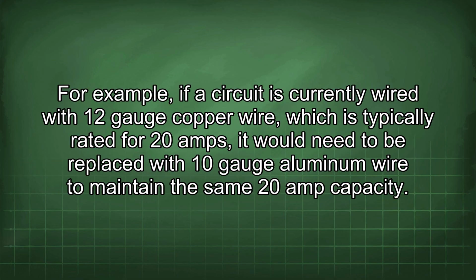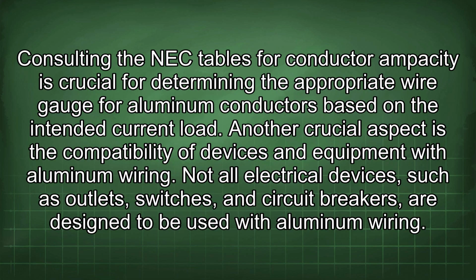ampacity. For example, if a circuit is currently wired with 12-gauge copper wire, which is typically rated for 20 amps, it would need to be replaced with 10-gauge aluminum wire to maintain the same 20-amp capacity. Consulting the NEC tables for conductor ampacity is crucial for determining the appropriate wire gauge for aluminum conductors based on the intended current load. Another crucial aspect is the compatibility of devices and equipment with aluminum wiring.